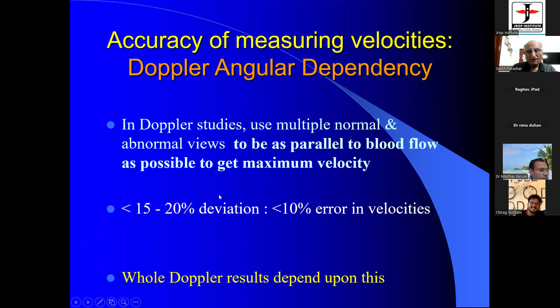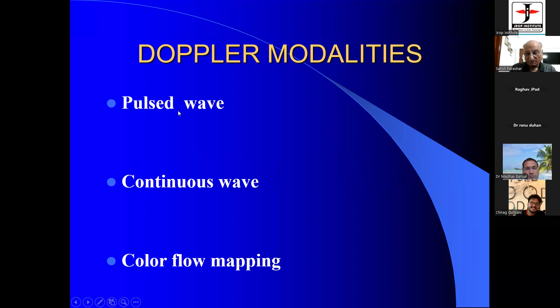Now there are three Doppler modalities. Remember, it is not difficult. One is pulsed wave, one is continuous wave, and one is color flow mapping. This is known as a sample volume. This is a pulsed wave. Wherever the sample volume is situated, you can only record from that place, and it only records a low velocity flow. In a continuous wave, it measures high velocity flow and there is no sample volume.